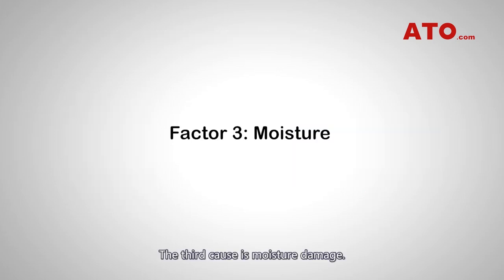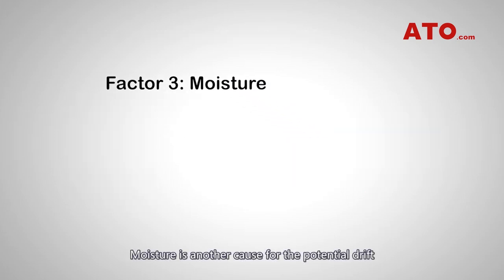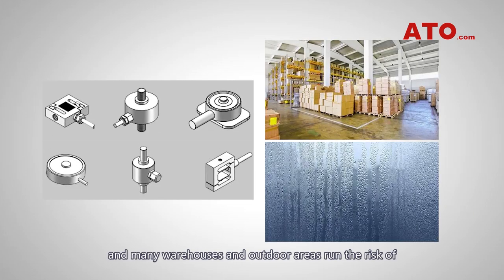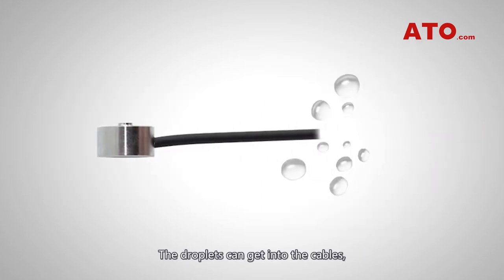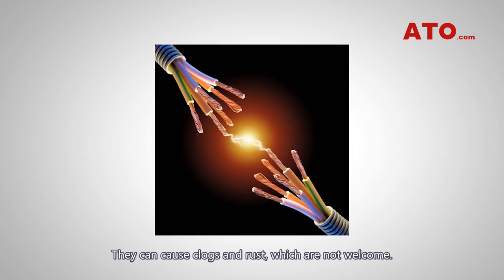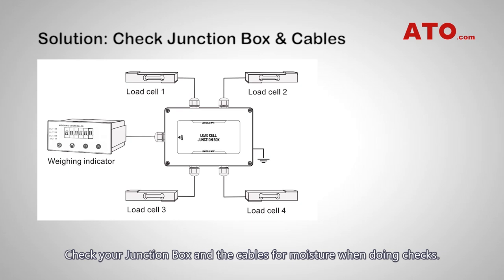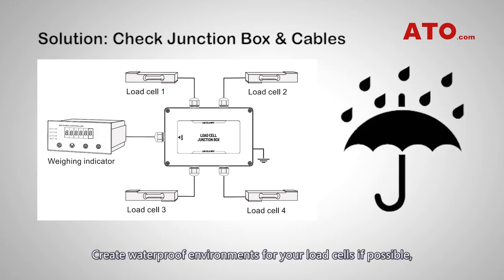The third cause is moisture damage. Moisture is another cause for potential drift, and many warehouses and outdoor areas run the risk of exposing a weighing system to excess droplets and vapour. The droplets can get into the cables, damaging them and the instruments inside the load cell. They can cause clogs and rust. Check your junction box and cables for moisture when doing checks, and create waterproof environments for your load cells if possible, doing what you can to remove potential humidity.